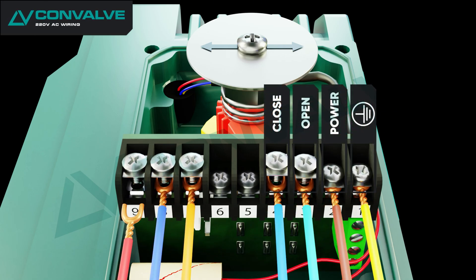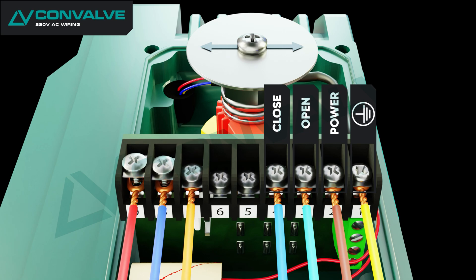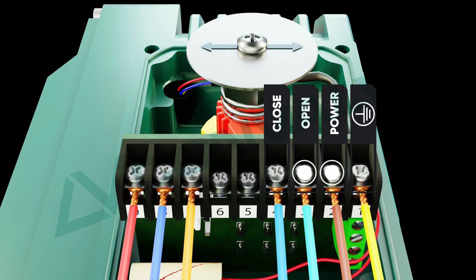To rotate or open the actuator in the counter-clockwise direction using AC voltage, apply power to terminal 2 and terminal 3. The actuator will rotate counter-clockwise until it reaches the internal limit switch and automatically shuts off.